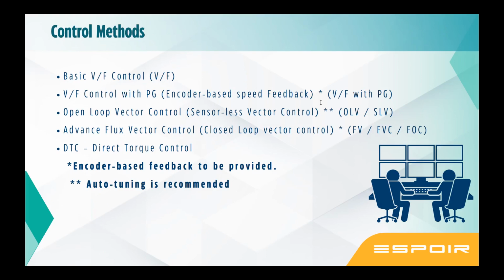During the tuning, the motor has to be idle. Means it should not be connected with any of the loads. No gearbox, no belts, nothing. It has to be just bare, otherwise tuning is not possible. So there are two types of tuning available. One is a dynamic auto tuning, another is a static auto tuning.